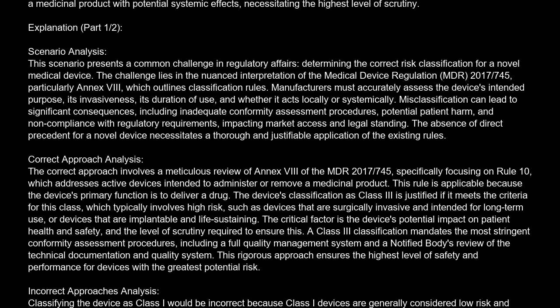2017/745, particularly Annex VIII, which outlines classification rules. Manufacturers must accurately assess the device's intended purpose, its invasiveness, its duration of use, and whether it acts locally or systemically. Misclassification can lead to significant consequences, including inadequate conformity assessment procedures, potential patient harm, and non-compliance with regulatory requirements, impacting market access and legal standing. The absence of direct precedent for a novel device necessitates a thorough and justifiable application of the existing rules.